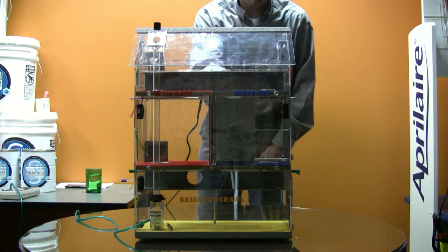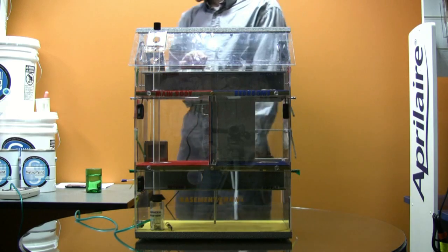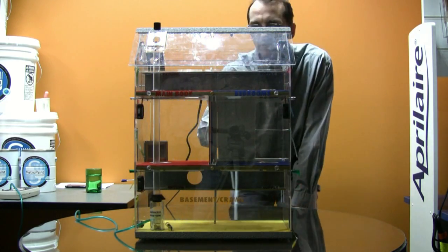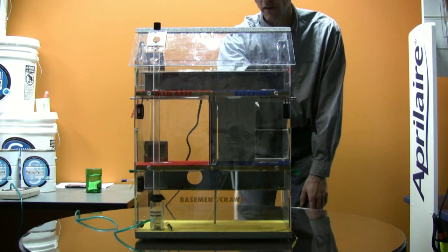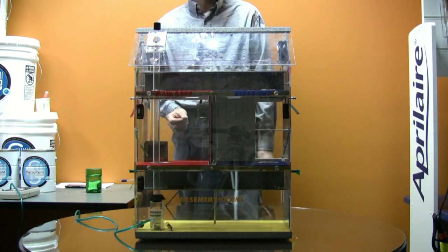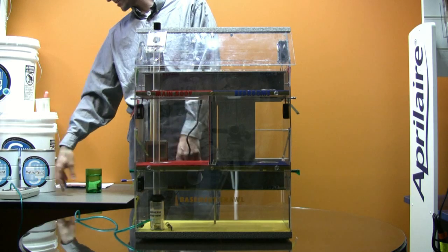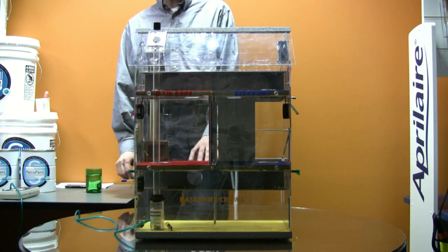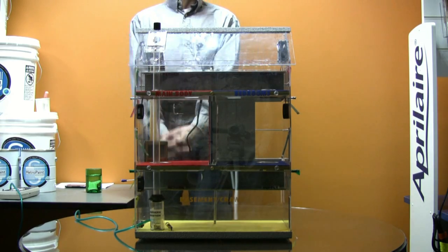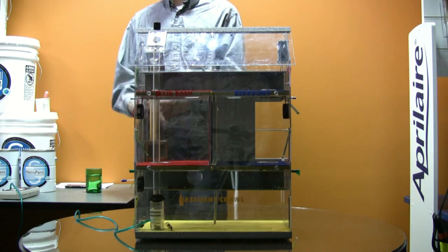So now I could even turn off these other fans in the house, and we might get our worst scenario. Nope, they're actually contributing slightly. So our very worst scenario that we've been able to create is with all our fans running and a leaky return in the basement. We've created a depressurization there of minus 1.8, minus 1.9 pascals. Then you have to ask yourself, okay, I just established my worst case scenario for this combustion zone. Well, what is 1.9 good for?